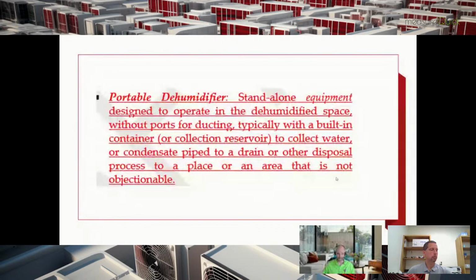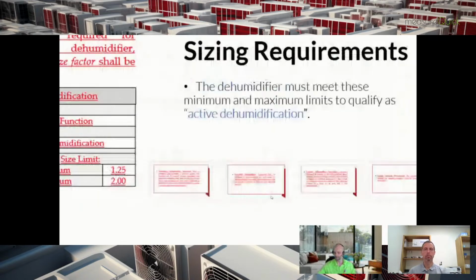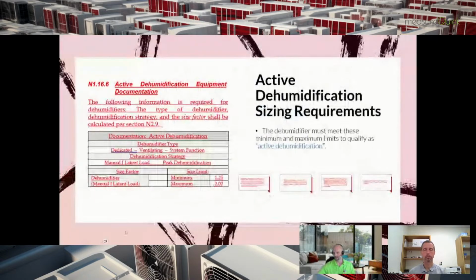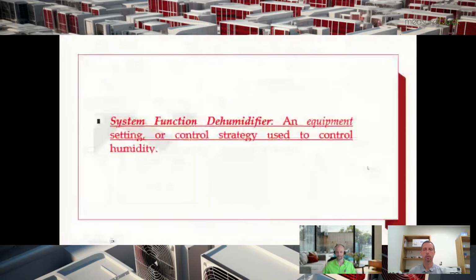If you've ever messed around with one of these things, you know you can take a condensate line and run it to a drain or something like that, but it ends up being a big hassle. These are the ones that were not listed in the acceptable active dehumidification here in the new Manual S. And then we do have this one here, and this is system function dehumidifier, an equipment setting or control strategy to use to control humidity.